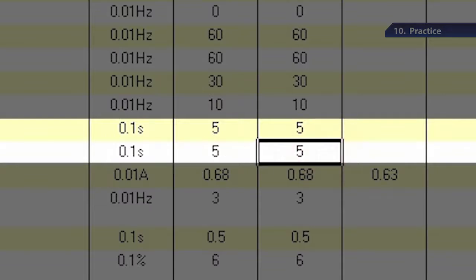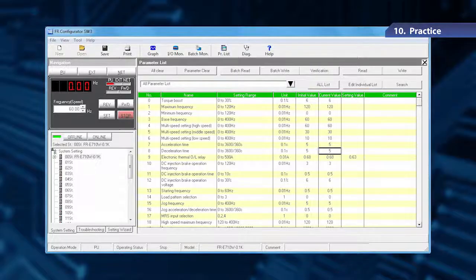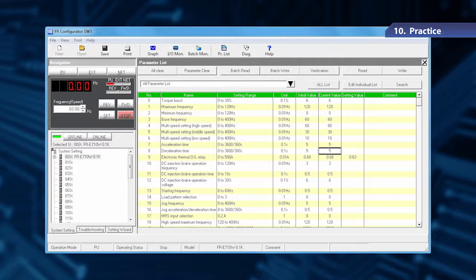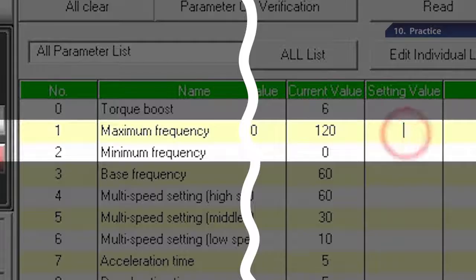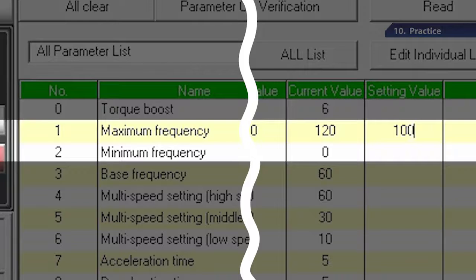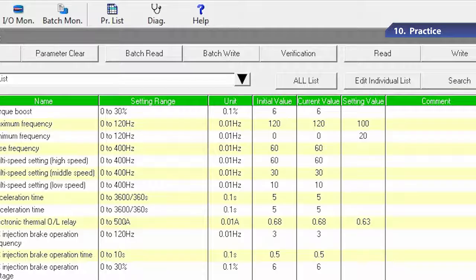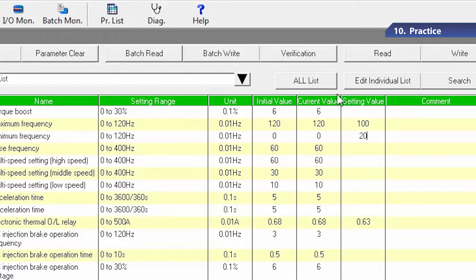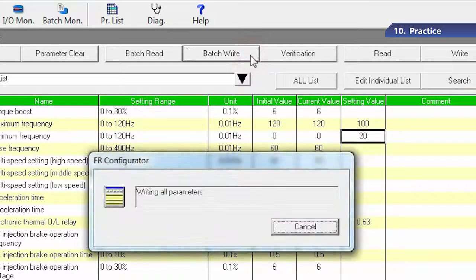Next, let's set the motor speed limit. Change parameter 1, Upper Limit Frequency, to 100 Hz, and parameter 2, Lower Limit Frequency, to 20 Hz. Click Batch Write to enter the new settings.